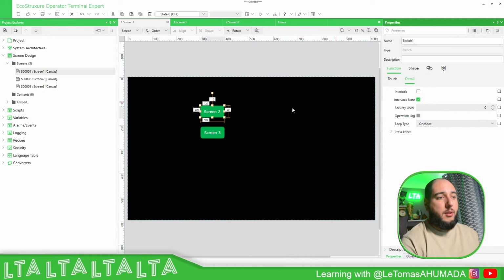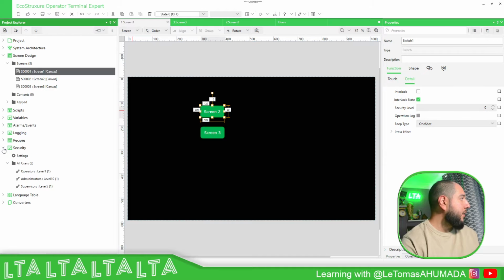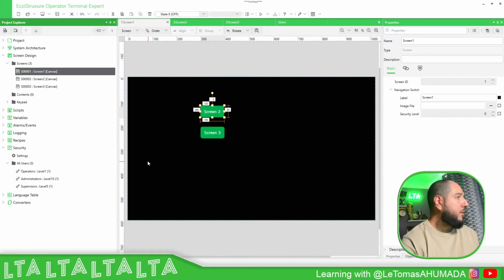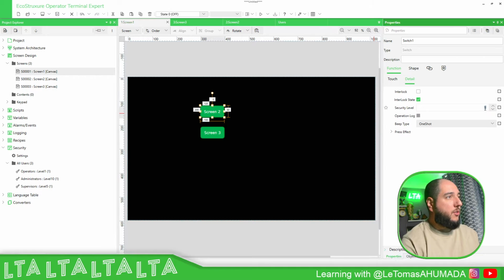The security level is linked to the security level that you have here. So over here, I'm going to specify security level 5. So everything above 5 is going to be able to use it. Below the 5, it isn't. So the operators will not be able to access this. And then at screen 3, I'm going to specify the minimum level as 1.